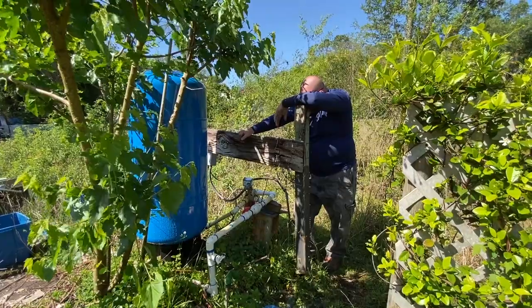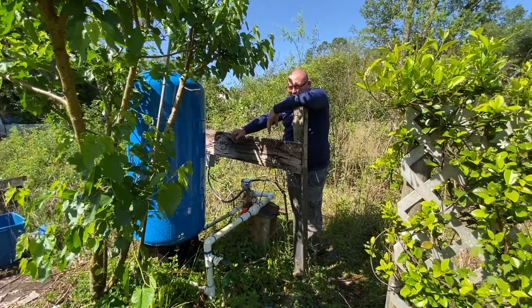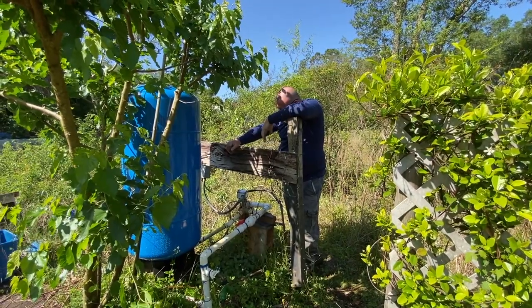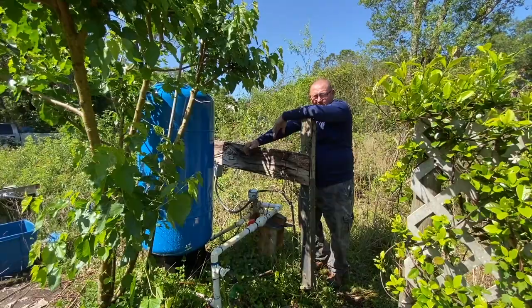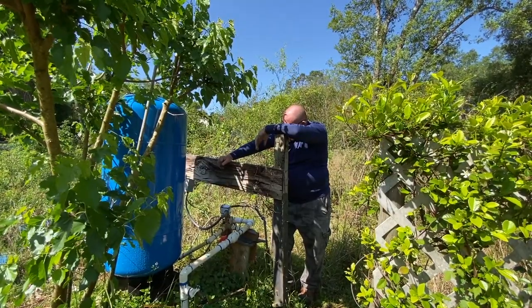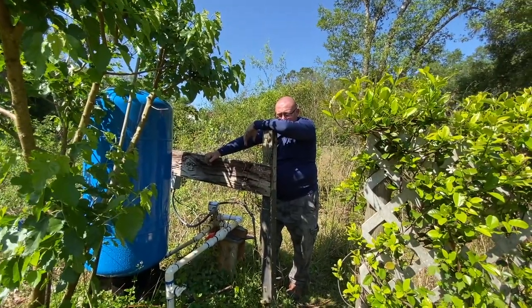So what is it set at to click off? About 40 to 60 — clicks on at 40 and off at 60. And this is 86 gallons compared to the old 20 gallon.